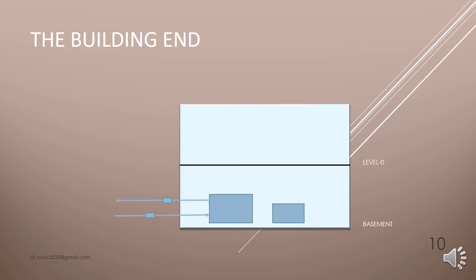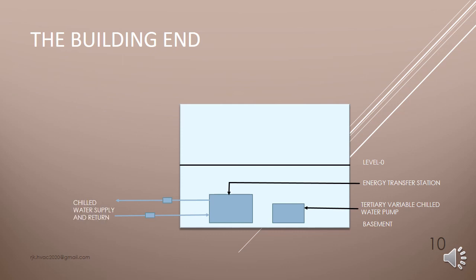The building end. This is a basic schematic section diagram indicating the location of equipment at the building end. So in the basement, we can have energy transfer station and tertiary variable chill water pumps. Chill water supply and return, either routed through utility corridor or buried, will be connected to the energy transfer station. BTU meters and PICV valves will be installed in the supply and return run respectively.